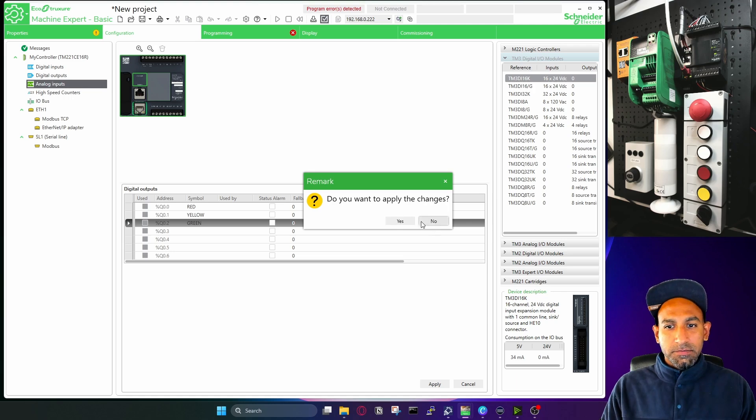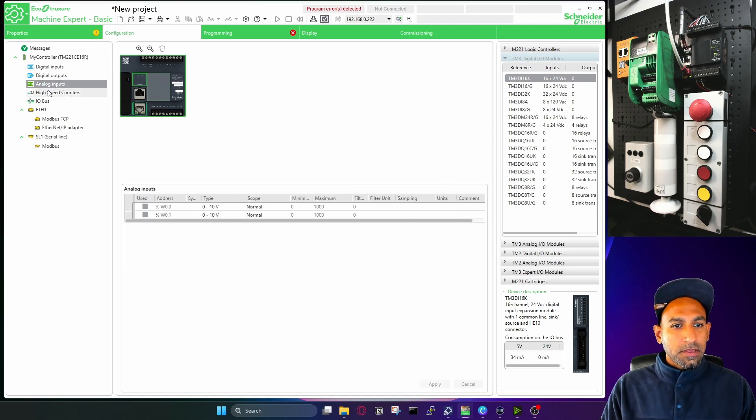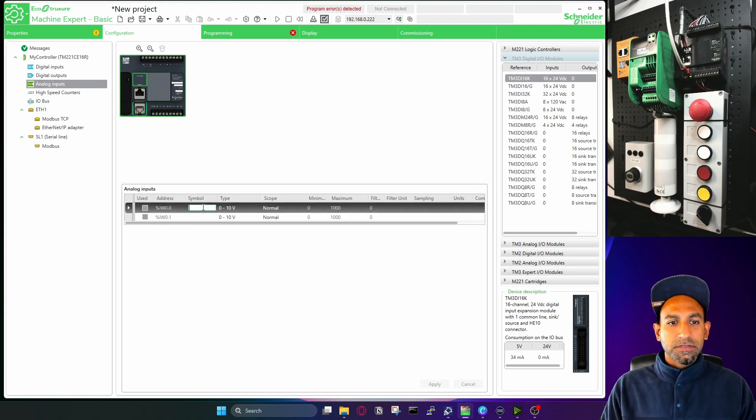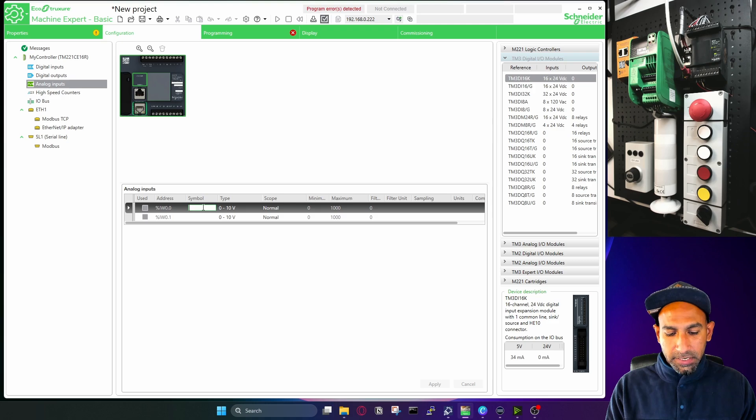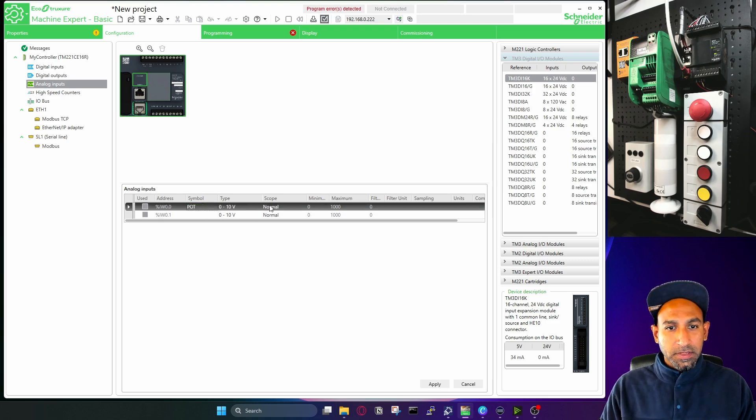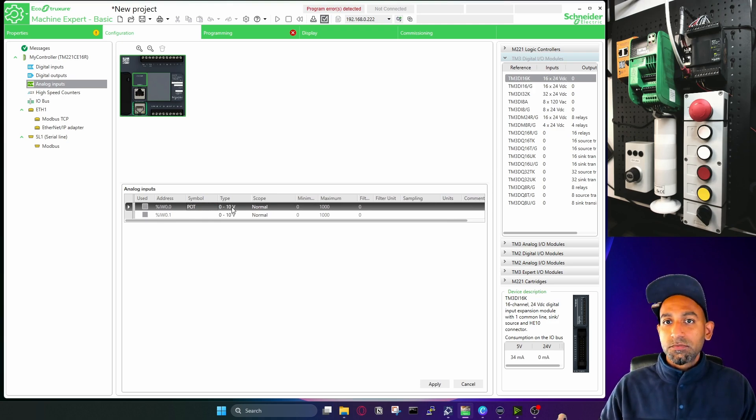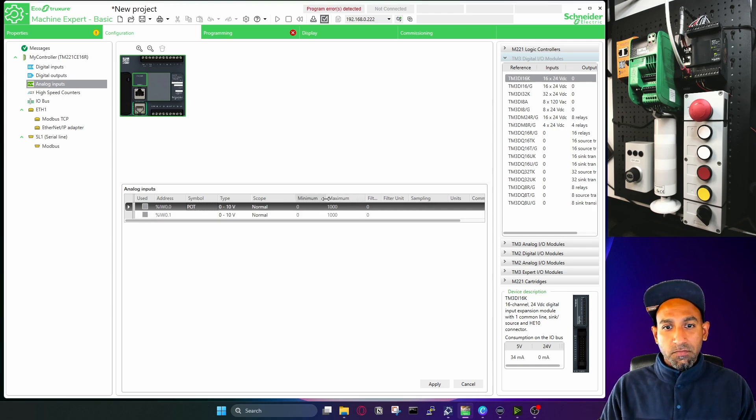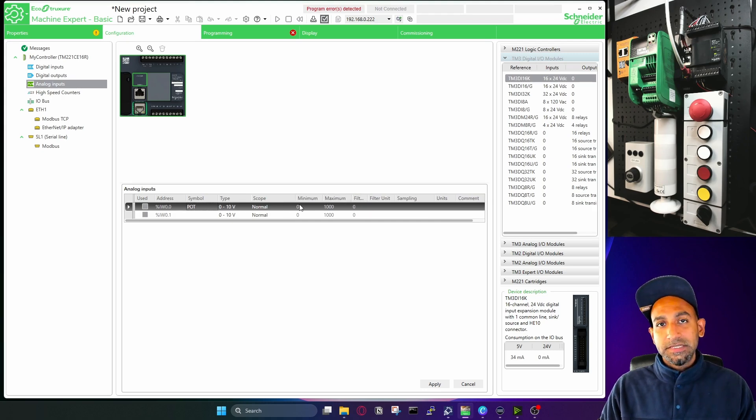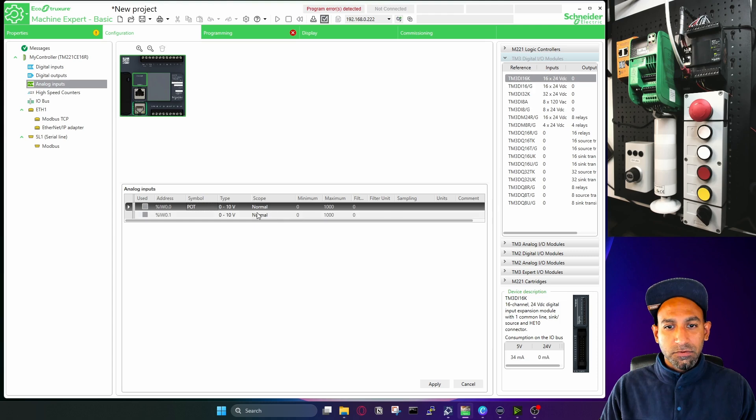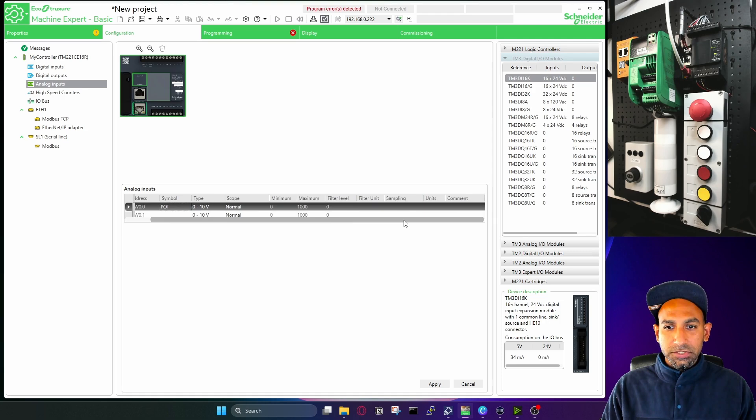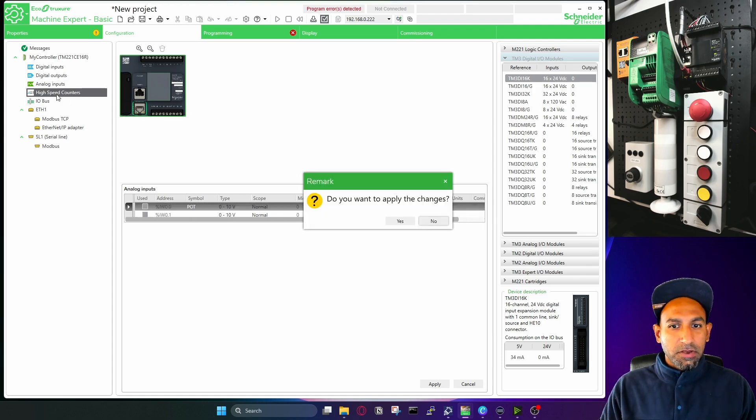Then you have analog inputs, again, applying changes. Analog inputs are addressed here. And these are the symbols. So the first analog input, I will connect it's not already connected yet to a potentiometer. So I can write a simple pot. And then you can see the voltage range zero to 10 volts. It's not minus 10 to plus 10, which is in most of the PLCs as well. But here is zero to 10 volts. And then you have minimum and maximum value which will come when you convert the voltage from zero to 10 volts. If it's zero, the value will be zero, the decimal value. If it's 10 volts, it will be 1000. So you can easily do the scaling. Filter level, filter unit, this will come later when we talk about analog inputs.